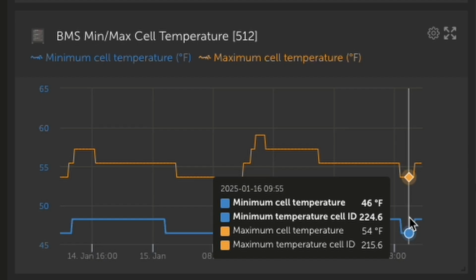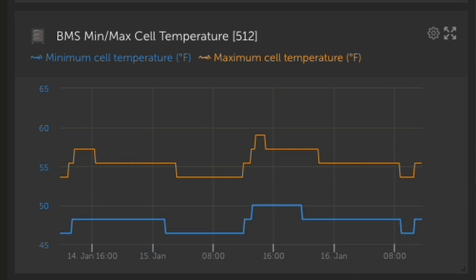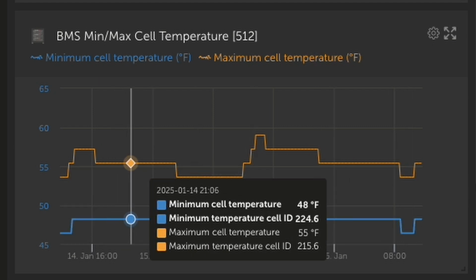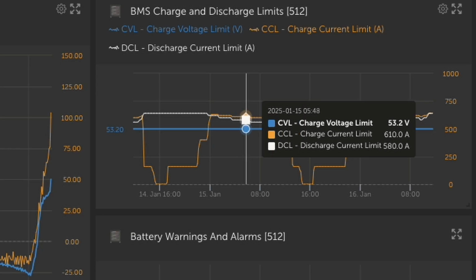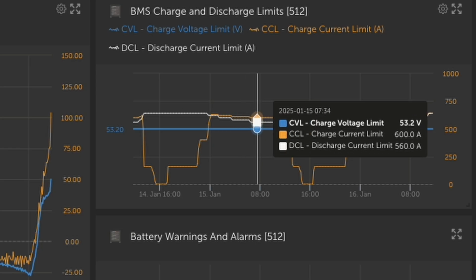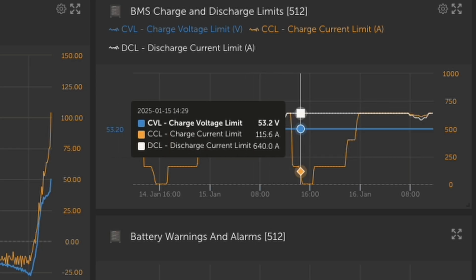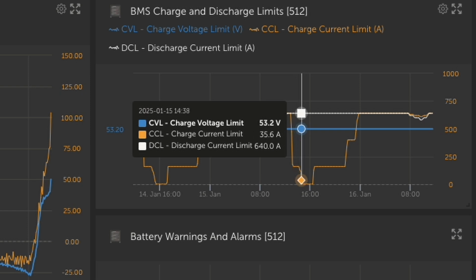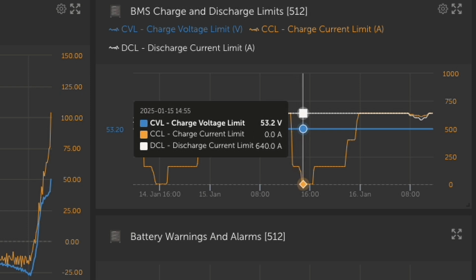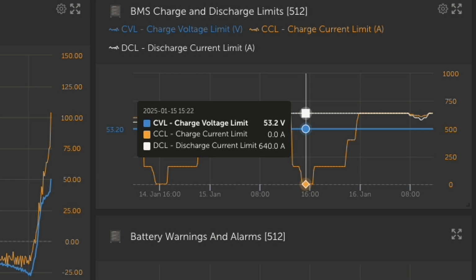Next one we're going to look at is the minimum and maximum cell temperatures. And we do see a little bit lower of a cell temperature here. Minimum cell temperature, 46 degrees Fahrenheit. And you'll notice the charge-discharge current limit adjusts ever so slightly, likely because of that minimum cell temperature. It didn't want quite as much amperage coming into the system. So very sophisticated, very thorough back and forth. The amount of information and control that the battery has is really impressive.